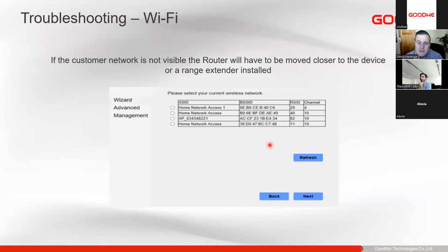As we know, Wi-Fi can be very unstable when there's very low signal strength, or if there is any object such as a microwave, because this is 2.4G Wi-Fi only. If there is anything like a microwave or something between the access point and the inverter itself, we can see a lot of disconnections, and constant disconnecting might result in it not reconnecting back to the network. So it's always good to make sure that our signal strength is sufficient. What I'd recommend is 50% or above signal strength, just to make sure that interference cannot result in a disconnection.